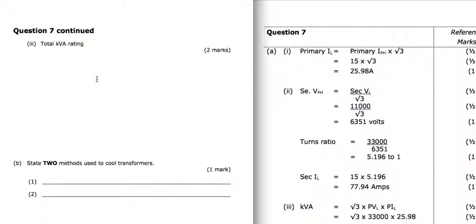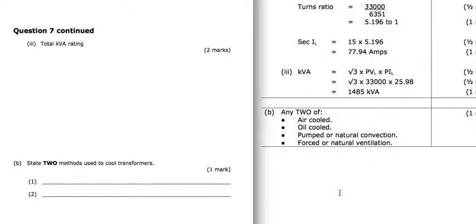We're asked to find the total kVA rating. So our kVA equation is √3 VL IL, and we can do this with either the primary or the secondary. They've done it here with the primary. So √3, there's our primary line voltage, and there's our primary line current, and that gives us 1485 kVA.